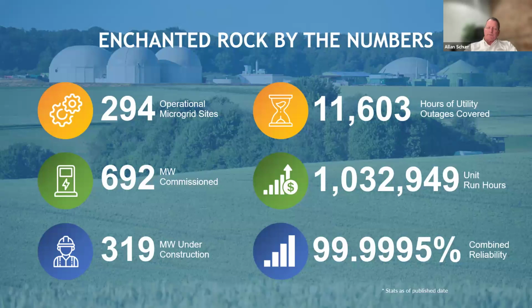We have a lot of experience with this technology and with a variety of different site conditions. The statistics related to the reliability of our systems show 5 nines of combined reliability when we look at the grid plus our ability to cover outages. It's extraordinary—better than diesel performance. We achieve that because we've had a lot of experience with utility outages, over 11,000 hours of utility outages at these 300 or so sites.